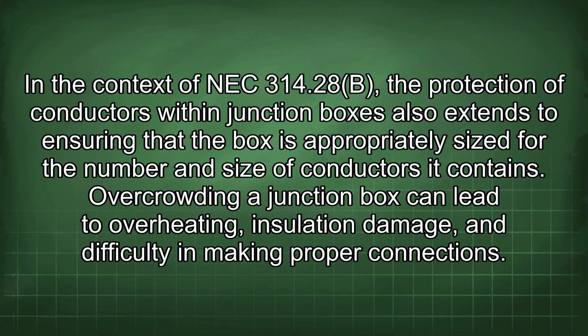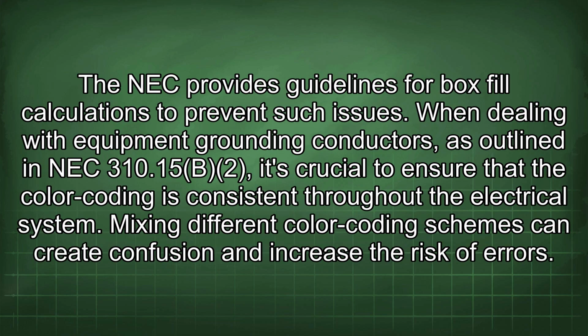In the context of NEC 314.28b, the protection of conductors within junction boxes also extends to ensuring that the box is appropriately sized for the number and size of conductors it contains. Overcrowding a junction box can lead to overheating, insulation damage, and difficulty in making proper connections. The NEC provides guidelines for box fill calculations to prevent such issues.